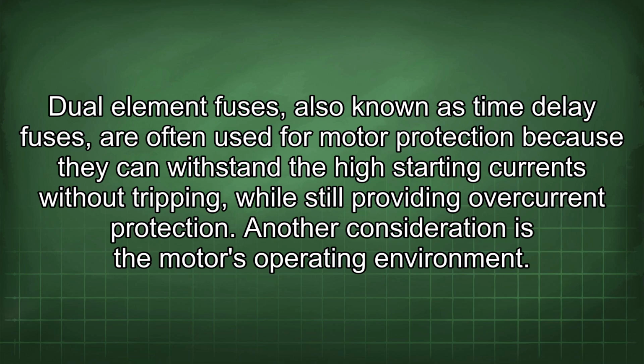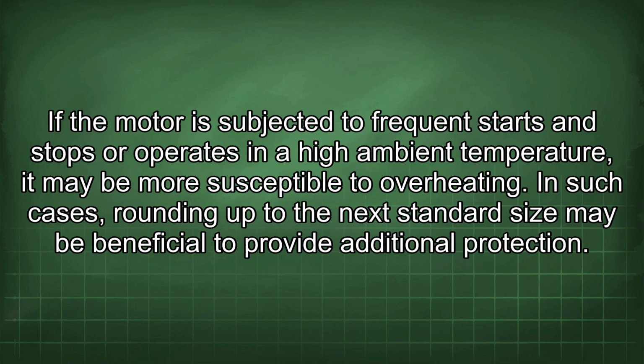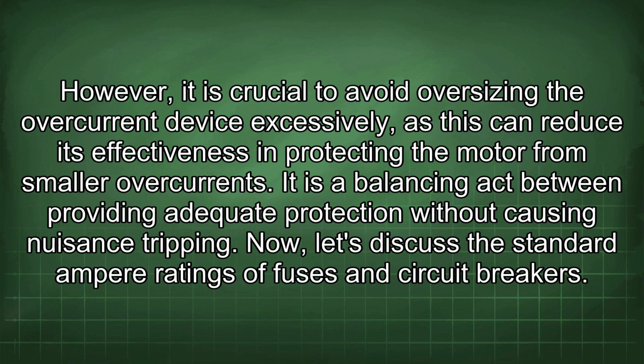Another consideration is the motor's operating environment. If the motor is subjected to frequent starts and stops or operates in a high ambient temperature, it may be more susceptible to overheating. In such cases, rounding up to the next standard size may be beneficial to provide additional protection. However, it is crucial to avoid oversizing the overcurrent device excessively, as this can reduce its effectiveness in protecting the motor from smaller overcurrents. It is a balancing act between providing adequate protection without causing nuisance tripping.